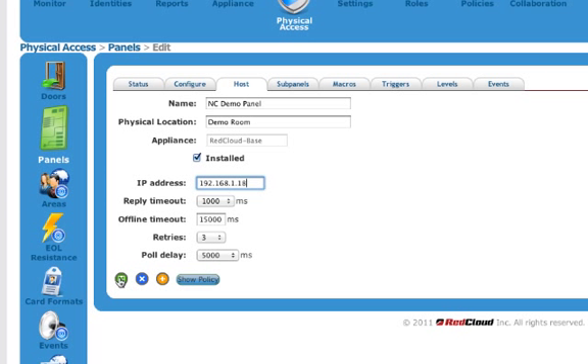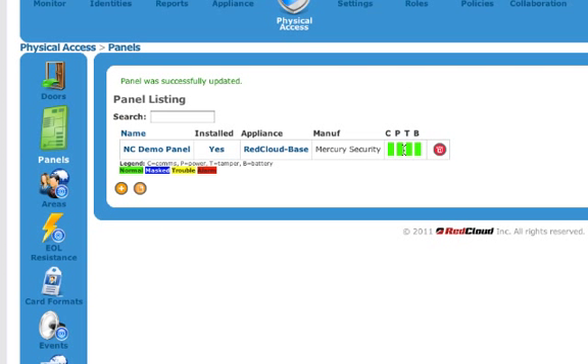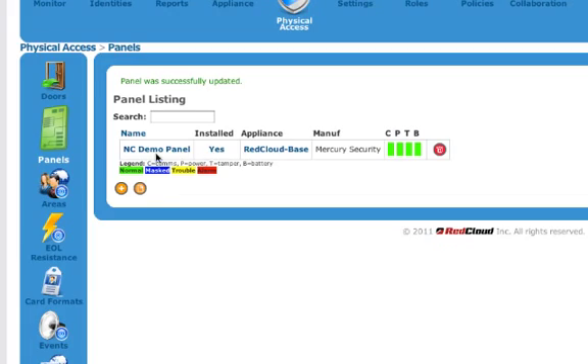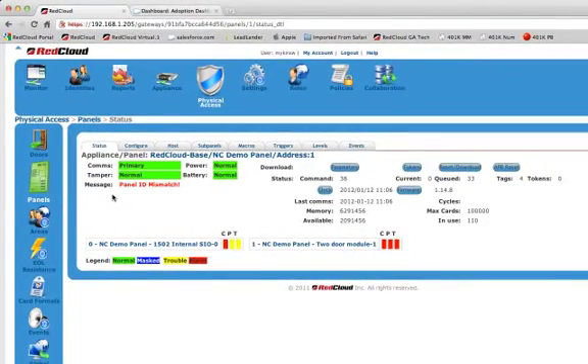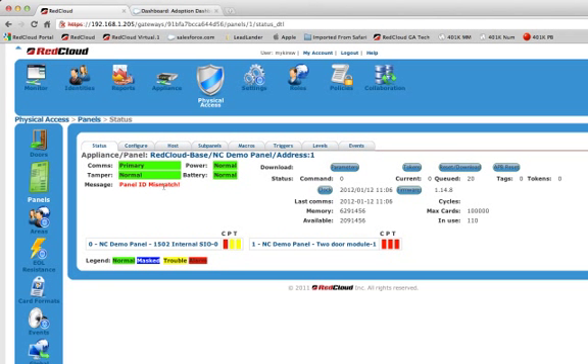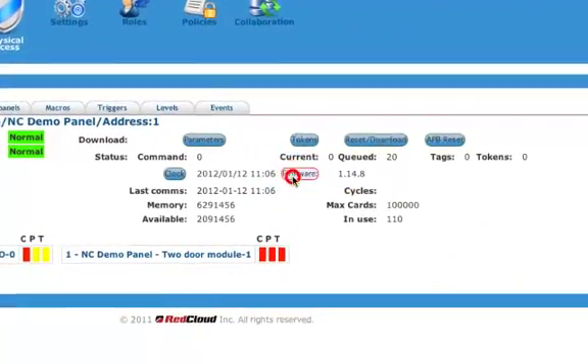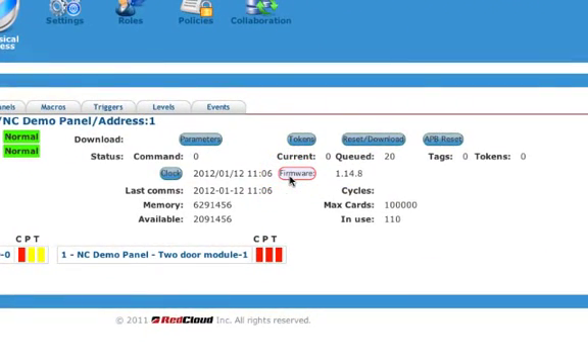So, I'm going to go ahead and hit save. It's going to bring me back to my main screen and you'll see the panel briefly come online, all green. So, we know it's communicating. The comms, power, tamper, and battery are all in green. So, I know it's communicating. My next step is to then click on the panel name. You can see that the panel ID has a mismatch to it. So, my next step is going to go in here, click on firmware.